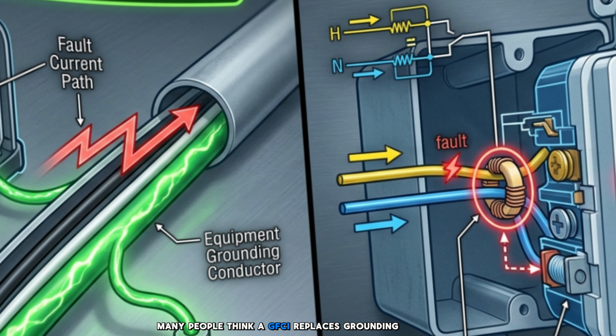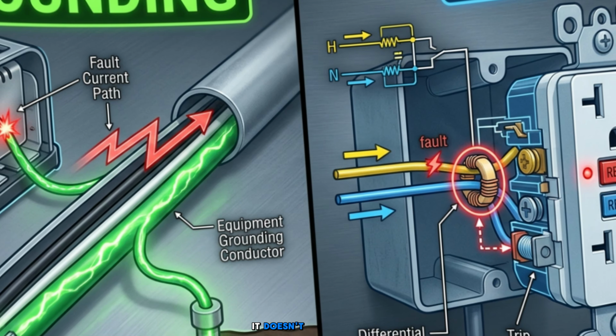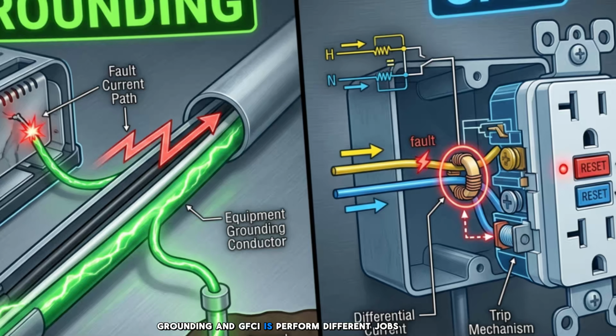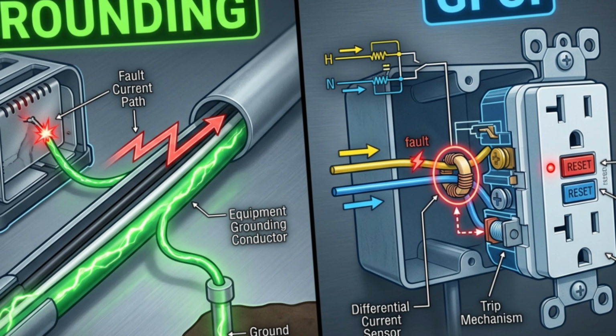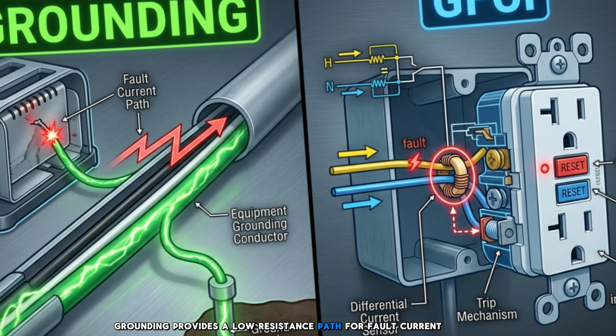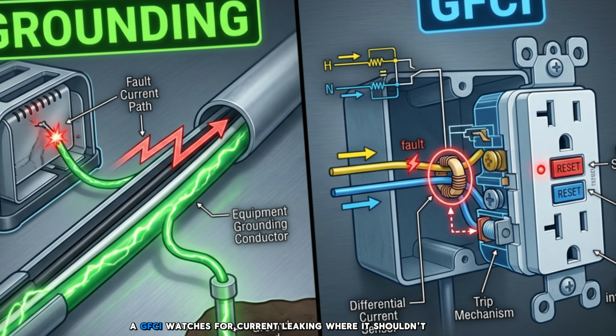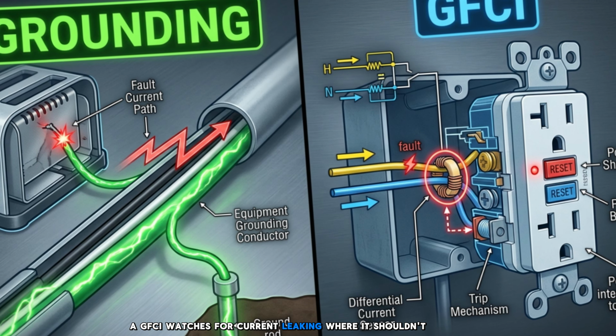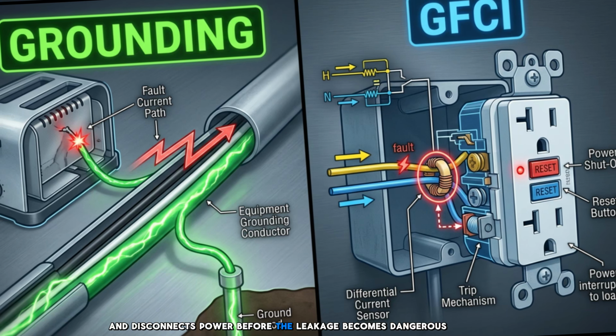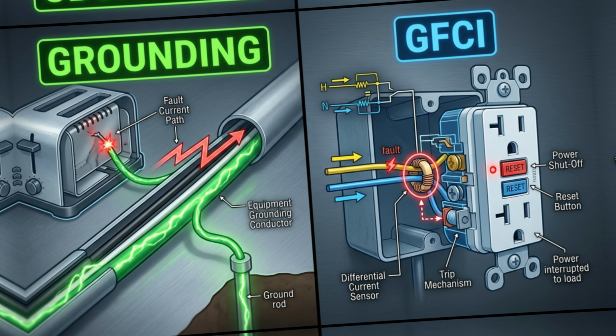Many people think a GFCI replaces grounding. It doesn't. Grounding and GFCIs perform different jobs. Grounding provides a low-resistance path for fault current. A GFCI watches for current leaking where it shouldn't and disconnects power before the leakage becomes dangerous. The safest electrical systems use both.